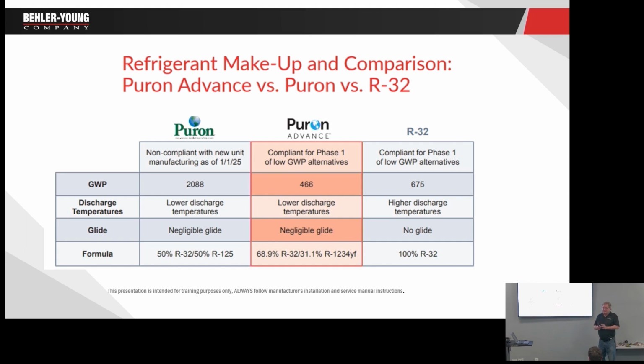But the good news is, if your helper screws up and puts 454B in your R410A recovery cylinder because he didn't listen, it's 50% R32, so it's not dangerous. I can't use it if it's mixed. We shouldn't mix it, but it's not a dangerous mixture if it gets mixed, okay? Because, again, 410A is a big part R32.